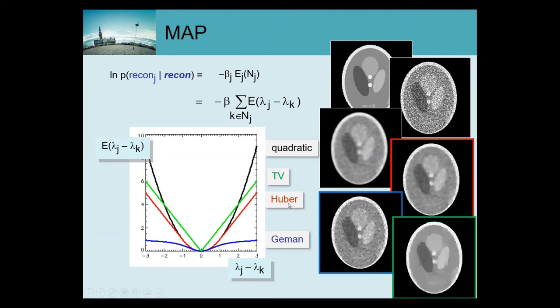There is a problem tuning these parameters, particularly for emission tomography, because it's much harder to predict what we'll see. For transmission tomography it's much more doable — we know we'll typically have soft tissue, bone, and important boundaries between tissue and lung. We know the contrast between lung and tissue, so we can say all differences larger than about one-third of that contrast might be data, and smaller differences are almost certainly noise. There is some uncertainty, but it would be much easier to find agreement on tuning, and our prior knowledge in transmission tomography is really much stronger than in emission tomography.